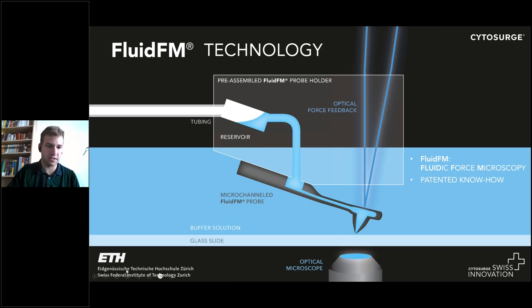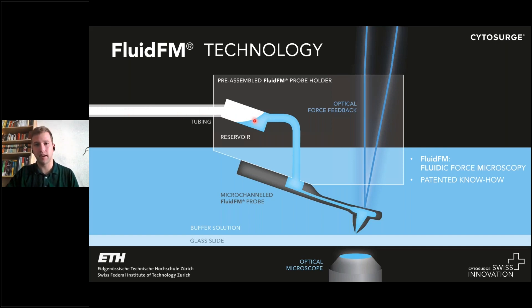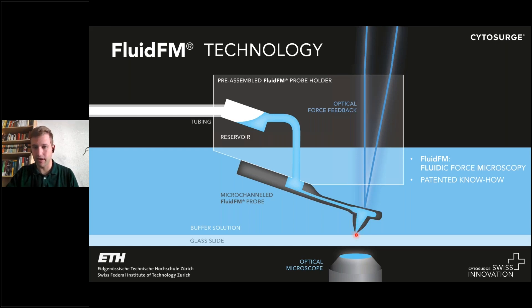The basic idea is very easy to understand. We have an AFM cantilever that has a microfluidic channel inside of it, going all the way from the tip to a reservoir, which is connected to a microfluidic pressure controller. This reservoir can be filled with one microliter of sample liquid that differs depending on the application. The channel goes all the way to the tip, where there is always an aperture.